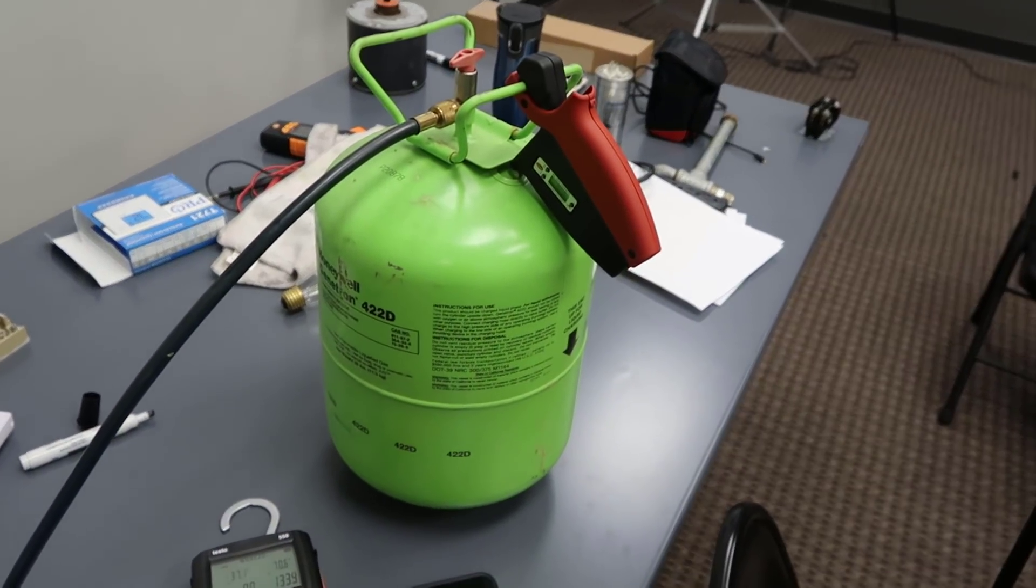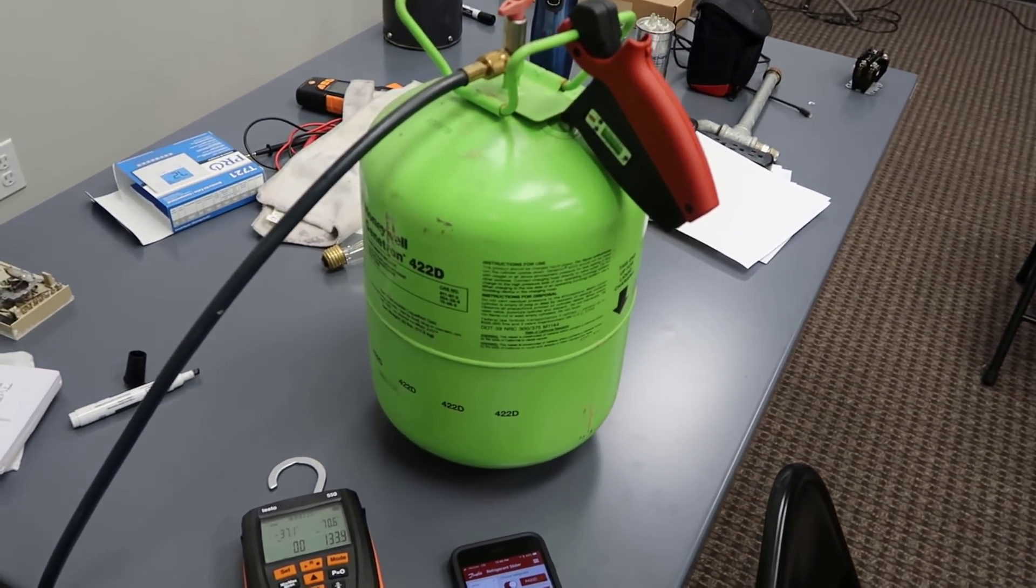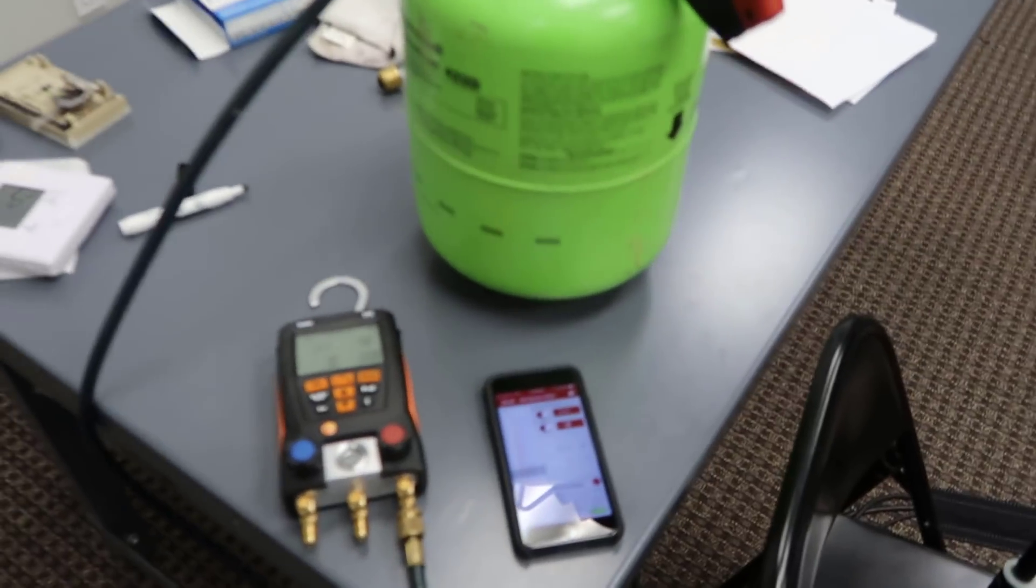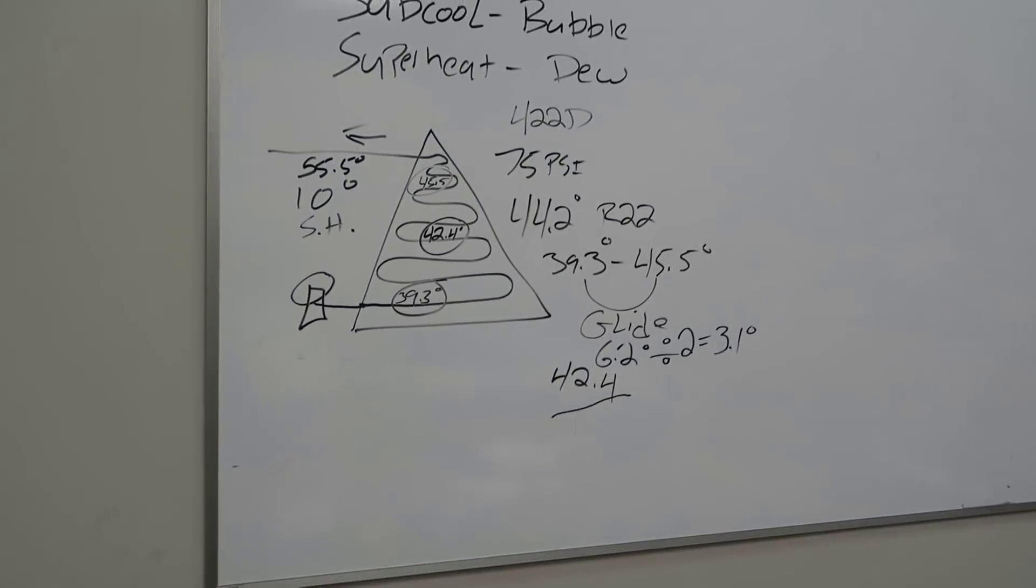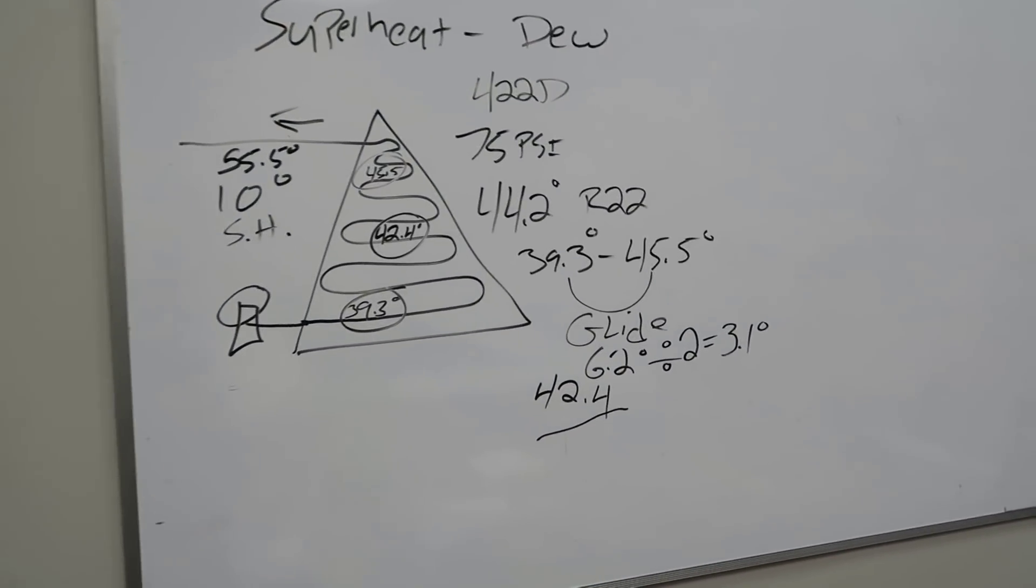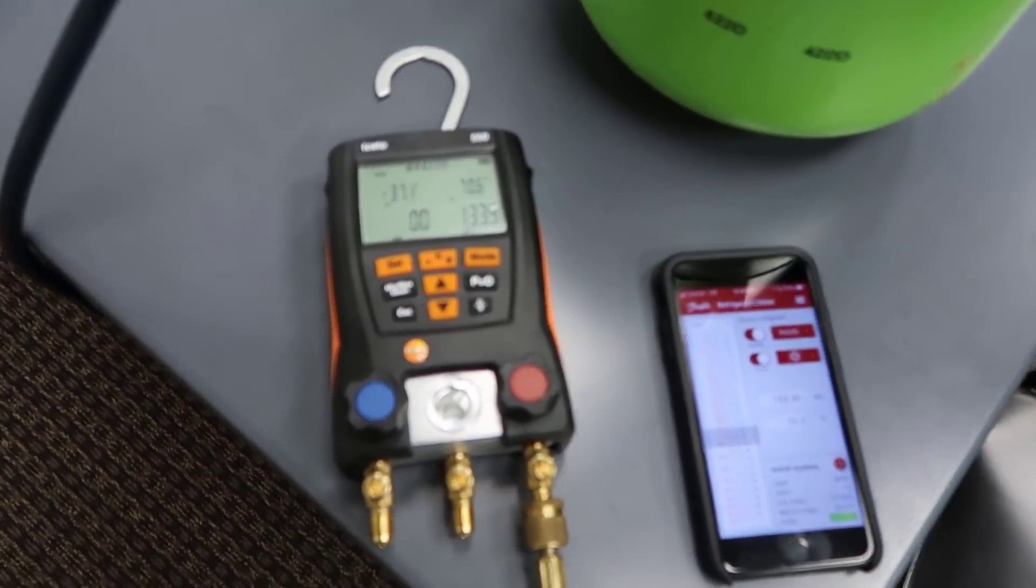So the only question is, if you have refrigerant in its static state, where it's just sitting still, what will it be? Will it be at dew point? Will it be at bubble point, or will it be at this median point, or middle point, or average between the two? And the answer is, and we're going to prove this, the answer is that it will be at the bubble point.